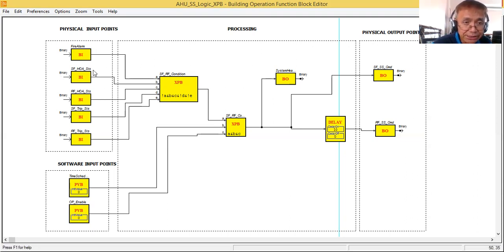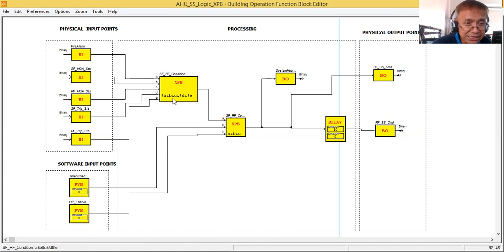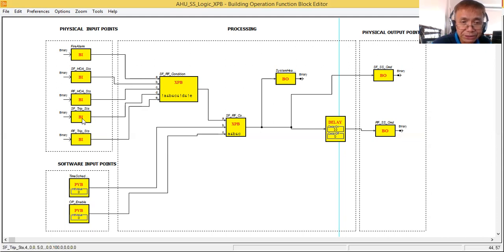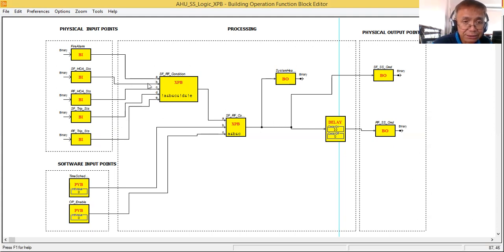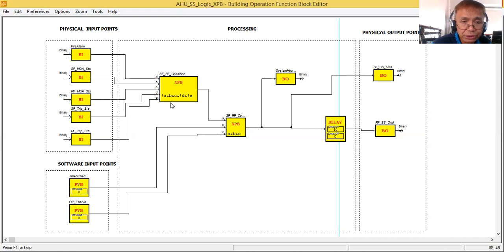B is the hand/auto status of the supply fan. AND C — C is the return fan hand/auto status. AND NOT D — meaning no supply fan trip status. AND NOT E — meaning no return fan trip status. So this expression is a combination of NOT and AND gates.